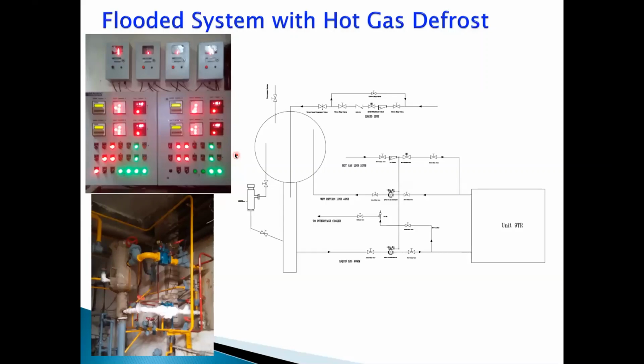A typical cold storage of 500 metric tons has 3 evaporators. Each evaporator has around 15 to 20 kilowatts of heater, and you need to run it for almost 45 minutes to 1 hour. With 3 or 4 evaporators in a room, you are spending more than 100 kilowatts for defrosting, which is a lot of waste and huge cost.